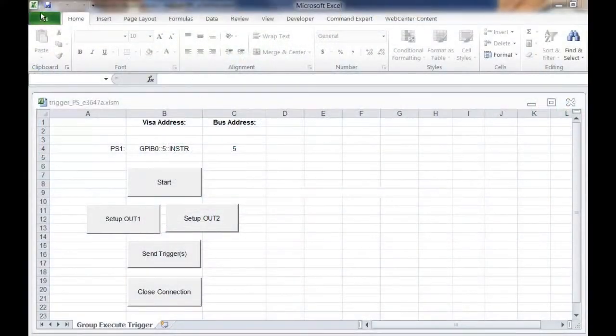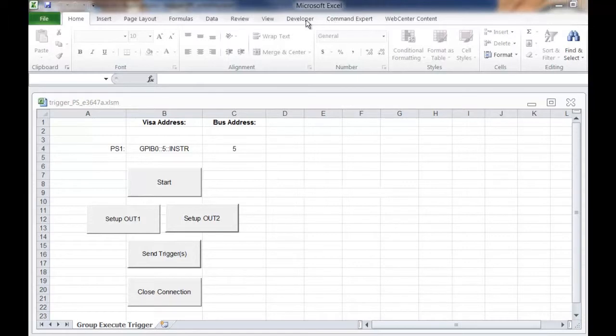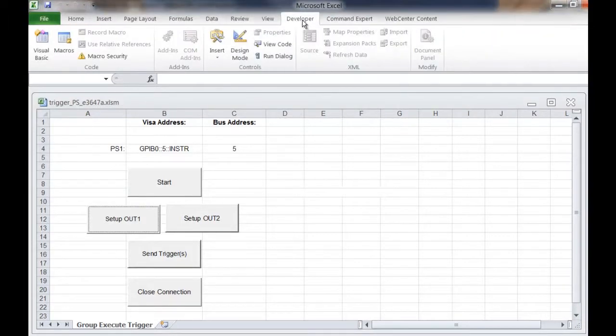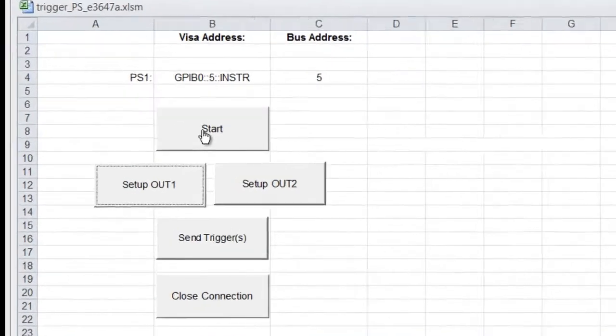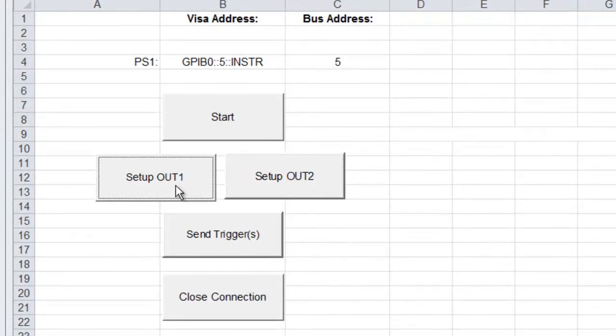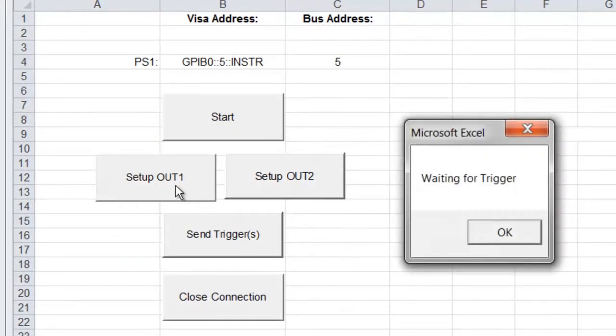We have a simple example program written in Visual Basic for Excel. So we'll go ahead and start our program, which opens our connection to the power supply and resets the instrument, and then we're going to set up each of the outputs separately.